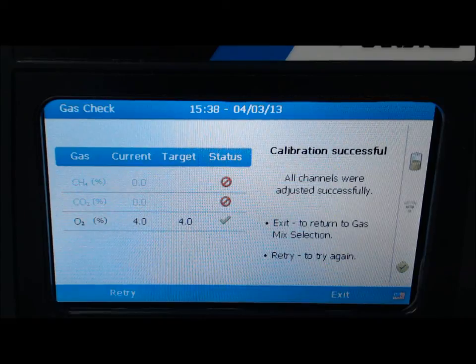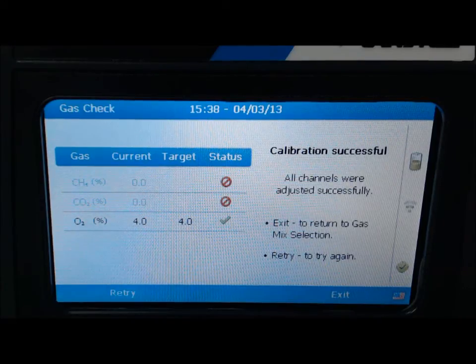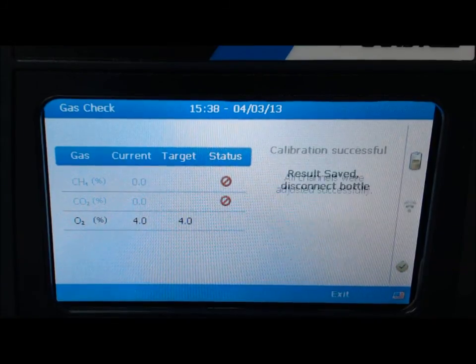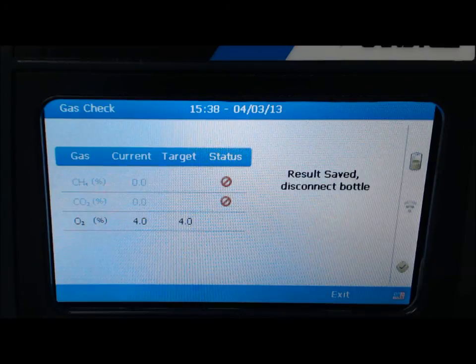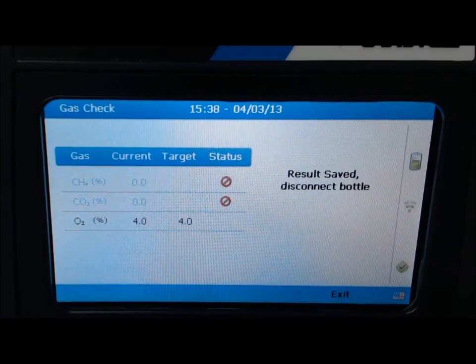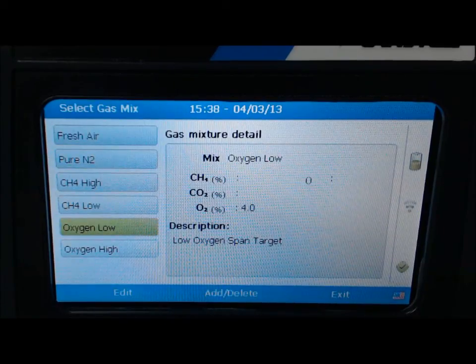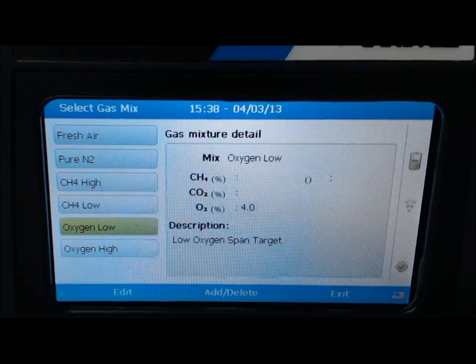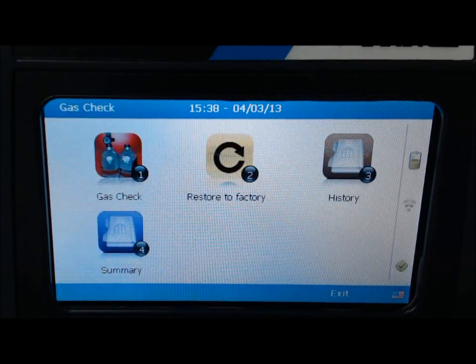At this point, you will need to turn off your pressure regulator, disconnect the hose, then select exit to save the results. Select exit once again to continue. You have successfully field calibrated your GEM 5000 instrument. Thank you.